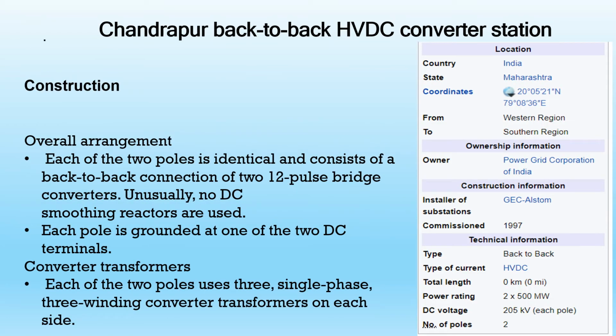Now let's take a quick look at construction. It has two poles. Each of the two poles is identical and consists of a back-to-back connection of 12 pulse bridge converters. Unusually, no DC smoothing reactors are used. Each pole is grounded at one of the two DC terminals. Each of the two poles uses three single-phase 3-winding converter transformers on each side.